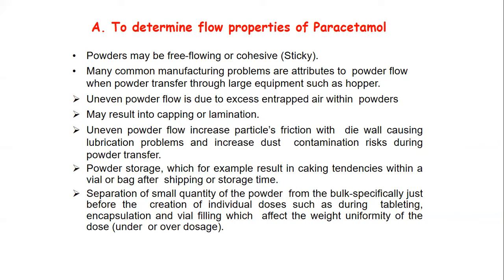Powders may be free flowing or cohesive, that is sticky. Many common manufacturing problems are due to powder flow when powder transfers through large equipment such as a hopper. The hopper is an important part, the feeding mechanism, of the rotary tablet press. Uneven powder flow is due to excess entrapped air within powders. So one of the reasons behind poor powder flow is excess entrapped air in the powder, which affects the flow properties.